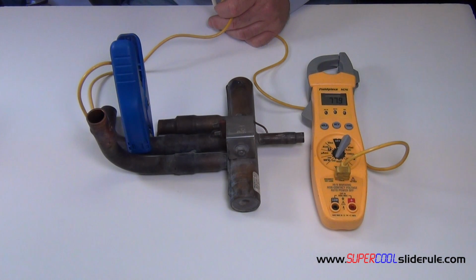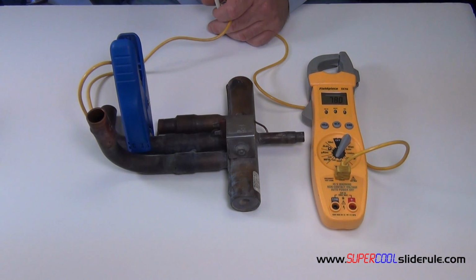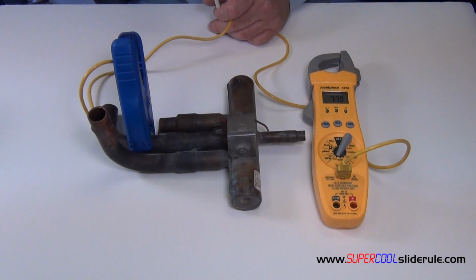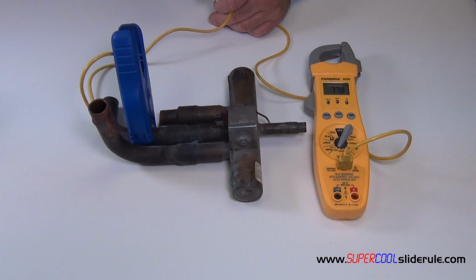But you may also have a bad compressor. Weak compressors will give very much the same symptoms as a bad reversing valve. So if you do have more than the 5 degree differential, also check the compressor. Go to our tutorial titled Compressor Testing Operation. Watch that tutorial to eliminate that possibility. This is all there is to testing a reversing valve.